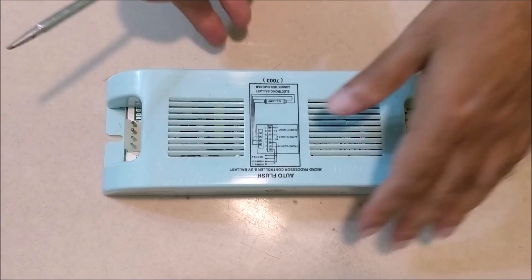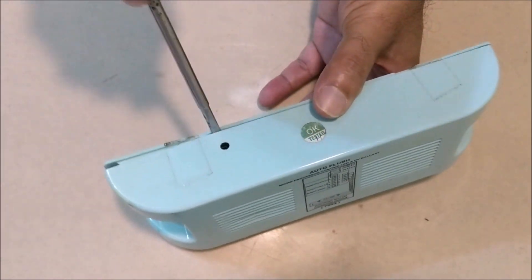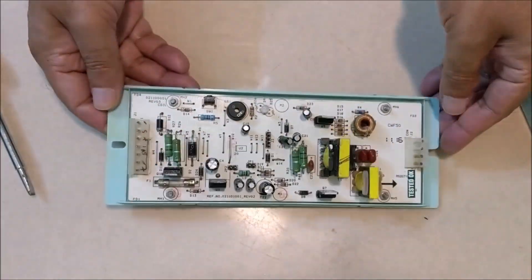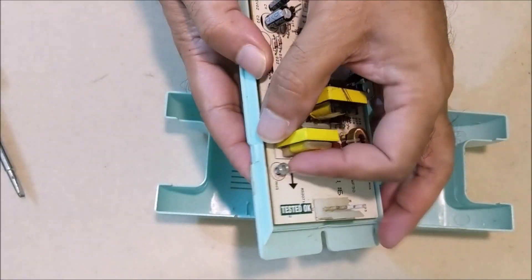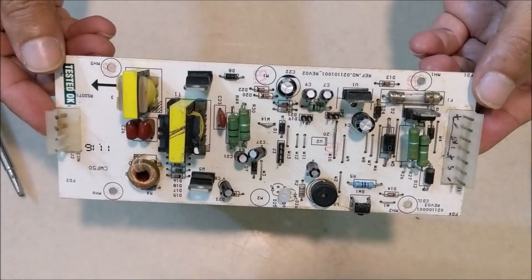If the water pressure coming into the machine is low, the machine will not run. And if the water storage tank is full, which is sensed by the float switch, then also the machine will not run. Let's open the electronic ballast and see what's in it. This is the circuit board of the electronic ballast.